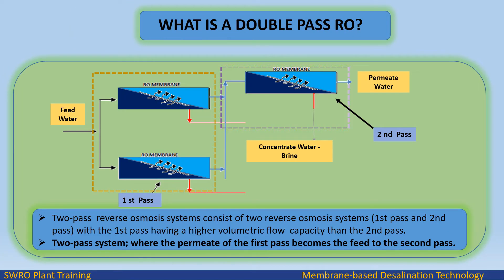Two pass reverse osmosis systems consist of two reverse osmosis systems — first pass and second pass — with the first pass having a higher volumetric flow capacity than the second pass. In a two pass system, the permeate of the first pass becomes the feed to the second pass.